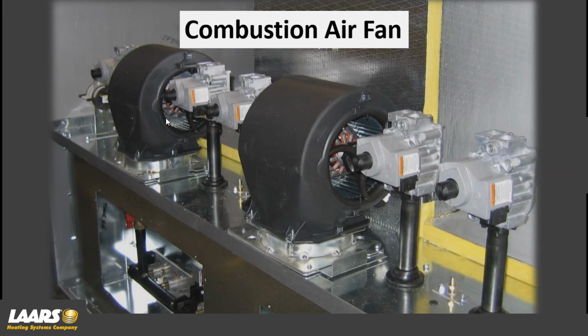So there's high and low. The second blower would run at a lower speed. Why? Because we want to keep some air pressure down in that right-hand portion of the chamber. If we had a high wind condition that contained some flue gases in the vent without tripping the switch yet, we don't want those flue gases traveling back through an unfired burner and into the combustion air for the plenum area. So they'll run the second blower at half speed.